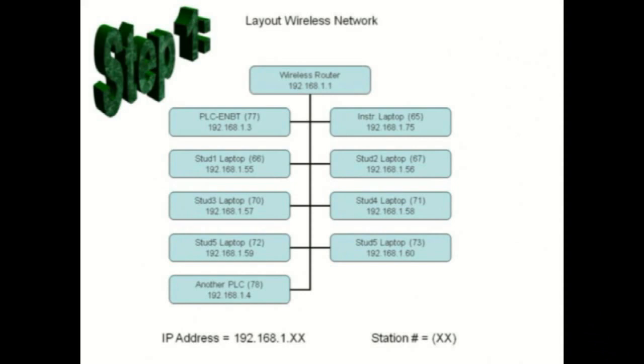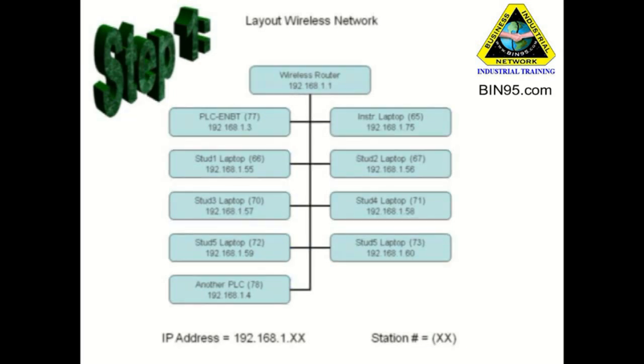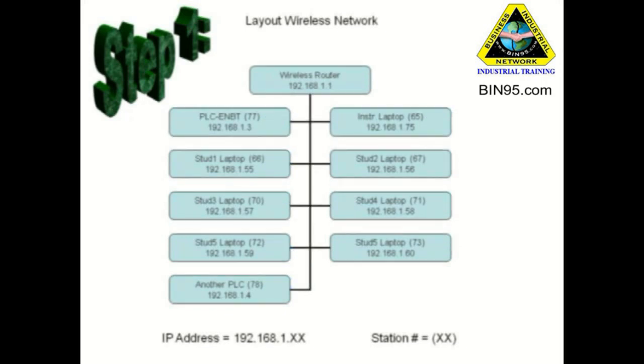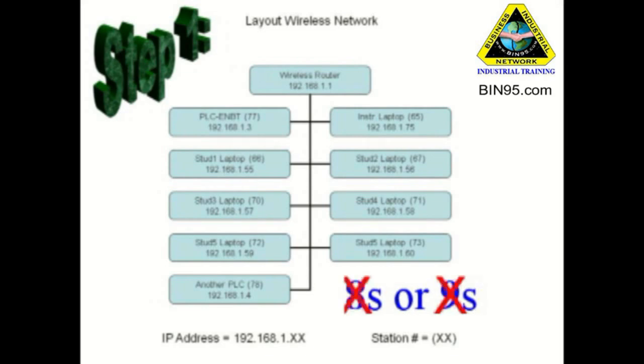The first part of step one is to map out your network. RSLinx is Allen-Bradley's communication software where you would set up the node addresses for Data Highway Plus. RSLinx and RSLogix also refer to these device addresses as station numbers. RSLinx Data Highway Plus likes octal numbers, which means we shouldn't be using any eights or nines in our addresses, in our two-digit addresses.